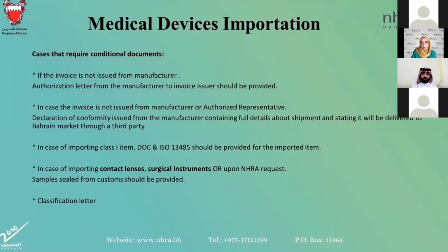I would appreciate it if, when continuing the question, you can copy the question itself, because I see comments, but I don't know which question those comments are related to. For COVID-related IVD items, can we use the declaration of conformity issued by the legal manufacturer as the CE approval requirement? You can only replace the CE with the reference country approval, emergency use approval, yes. I'm not sure why those questions are being raised, but let us explain the common sense behind the responses that we're providing you.